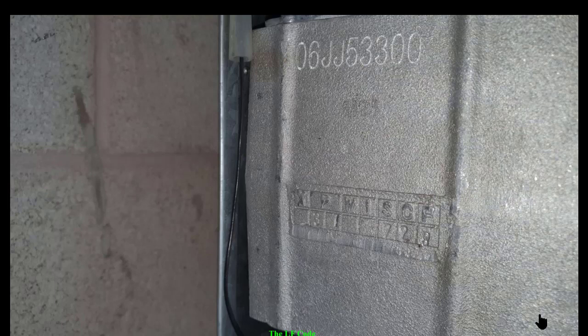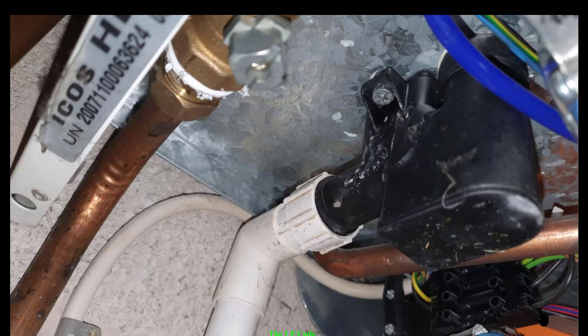That's what you do. Incidentally, on my Mastered Basics course, if you take that course, in the part where we talk about multimeter testing, we talk about this actual test, how you check the milliamps going from the flame sensing electrode to the PCB. So here's another tip why you will get the LF code, and that would be the condensate trap that could be blocked.